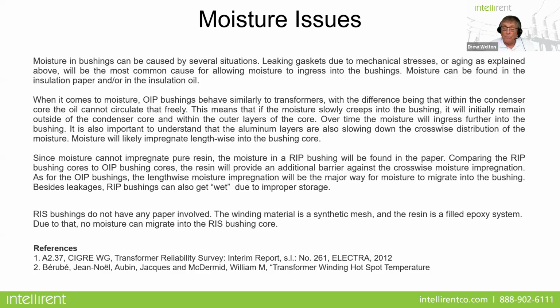Now, we had a customer that was storing these RIP bushings outside in a crate for quite a few years. When they went to take them out of storage and use them on a transformer during a bushing replacement, it was determined that every single one of them, we're talking about 25 different bushings, were all bad because moisture had impregnated the bushing itself. So lesson learned: store your spare bushings properly. Don't allow moisture to get in.